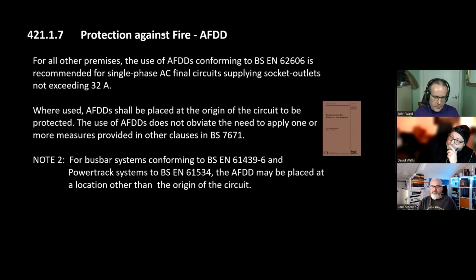Obviously, rings have their problems, with broken bits and overloading the conductors and all that anyway. But in terms of series arcs on a ring, it's not going to detect it, but then there's not going to be that amount of energy there to cause a fire anyway. So it doesn't matter. The structure of the ring itself kind of gets rid of that issue, doesn't it? Yeah. However, if you have a connected load that's pulling more than 2.5 amps, say a fridge or a heater, or a series arc on an extension lead plugged into the ring, then it should, in theory, still work. So I think Eaton's words to us when we met them was, we don't recommend it, because they won't give full performance guarantees that people would expect.